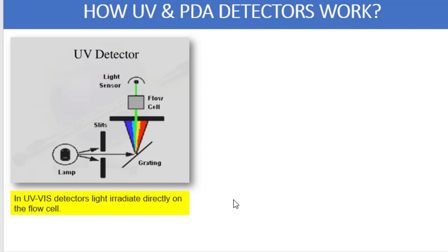This wavelength separation allows the selection of light with a suitable wavelength by using another slit. Suppose as a part of your analysis you want to determine the response at 254 nanometer, so that particular light generated by the diffraction grating will only pass through the second slit and then it will enter into the flow cell.